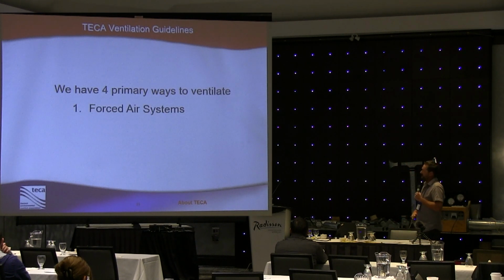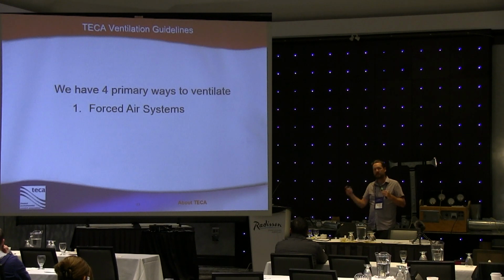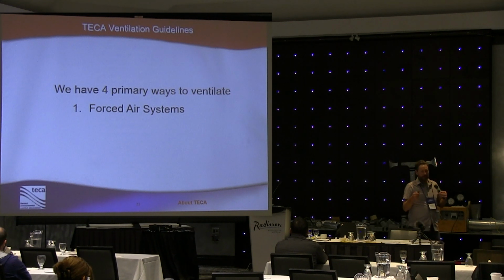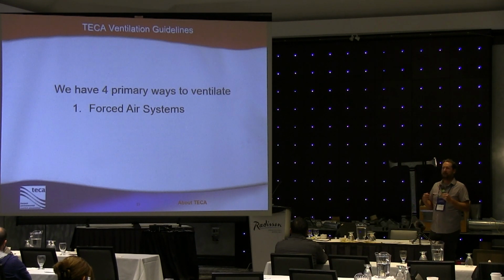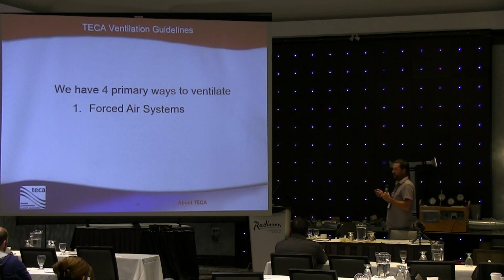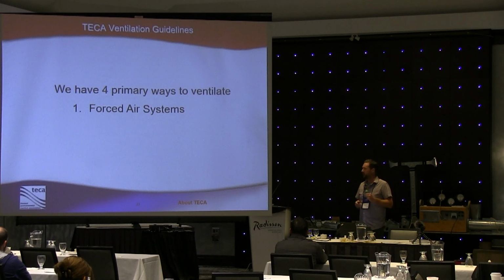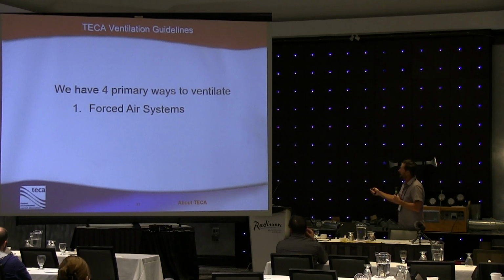So we've got forced air systems, and this is probably one of the simplest ways to ventilate a residence, using a forced air system. Now you have to have a forced air heating system, heating and cooling. Forced air heating and cooling systems have ductwork. The building code prescribes that we have to supply fresh air to every bedroom, and typically we supply that fresh air with the heating system, or the heating and cooling system, if you will. So if we're going to ventilate, it makes sense for us to use the existing ductwork that goes along with that forced air heating system. And I'll show you how that goes together here in a minute.